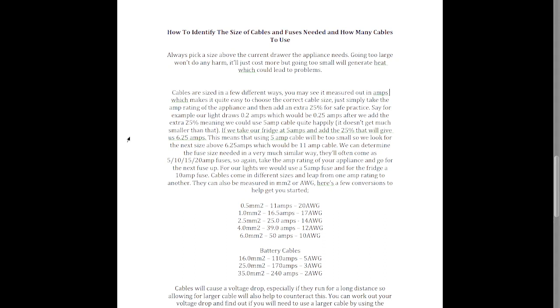That would mean we could use a 5 amp cable quite happily. Cables don't really get much smaller than 5 amp, that's why we've gone so much higher. If we take our fridge as an example, which would draw 5 amps, and add that extra 25%, it would draw safely 6.25 amps through a cable. That would mean 5 amp cable is too small, so we'd be looking for the next size above 6.25 amps, which might jump up to something like an 11 amp cable.